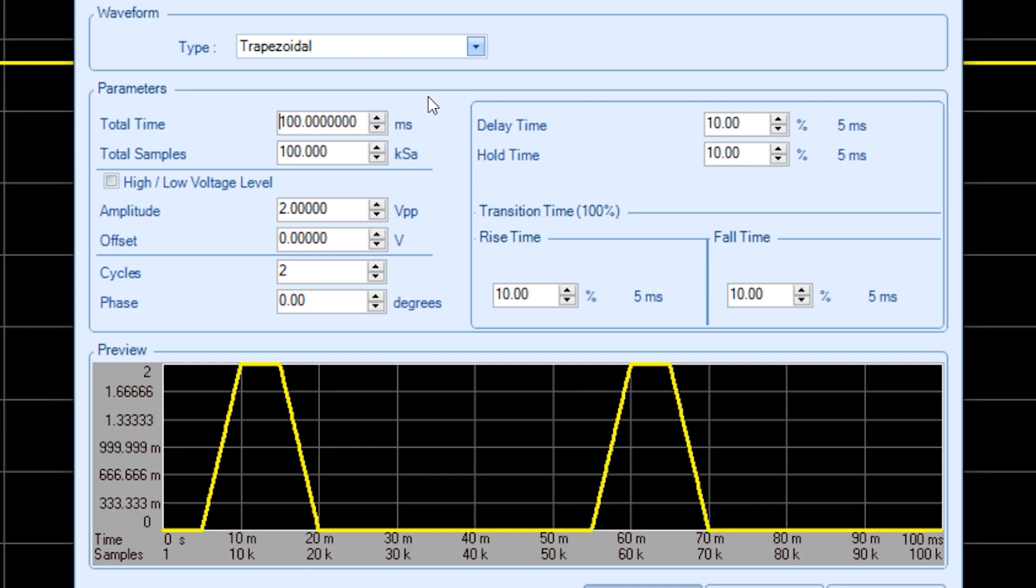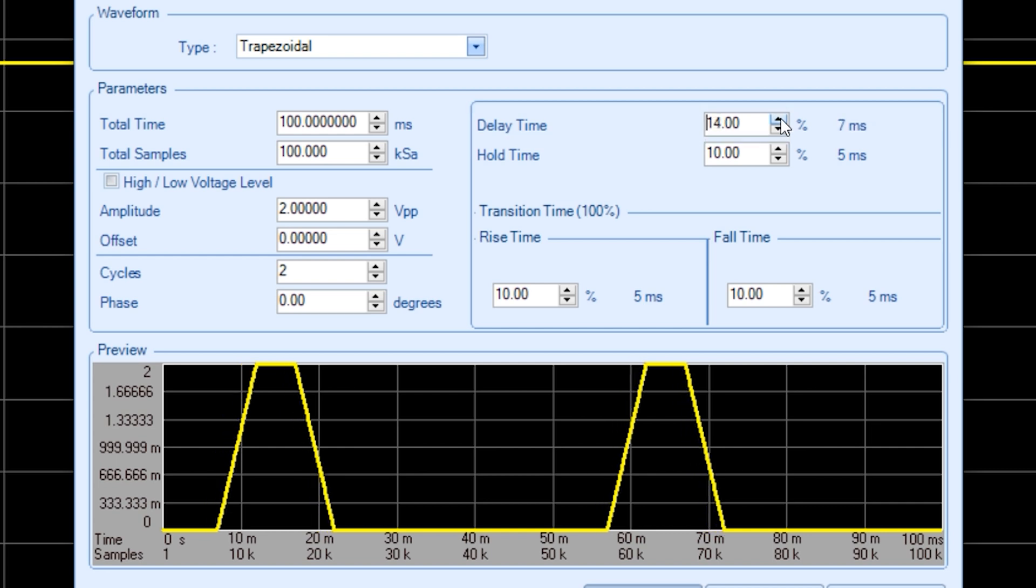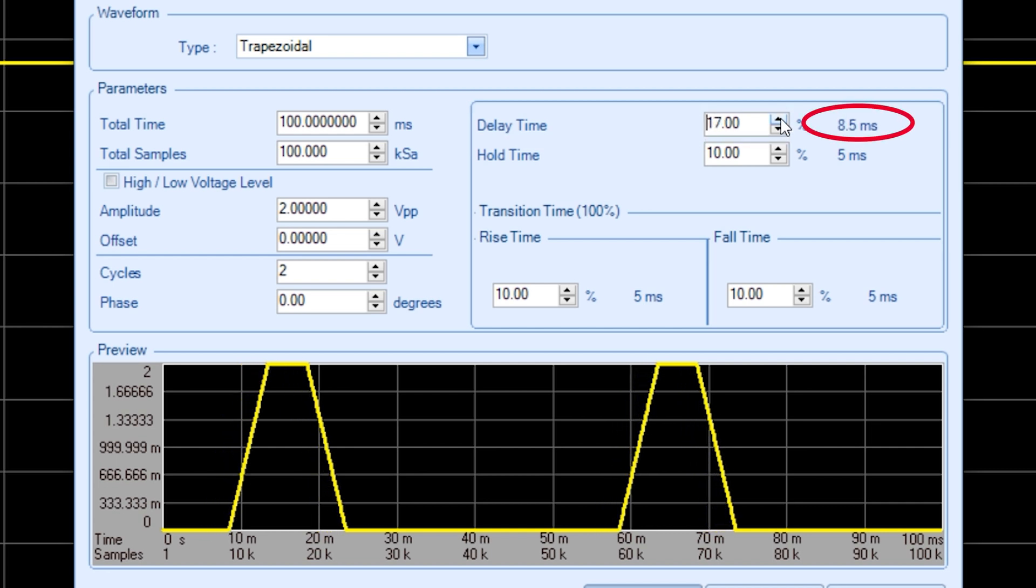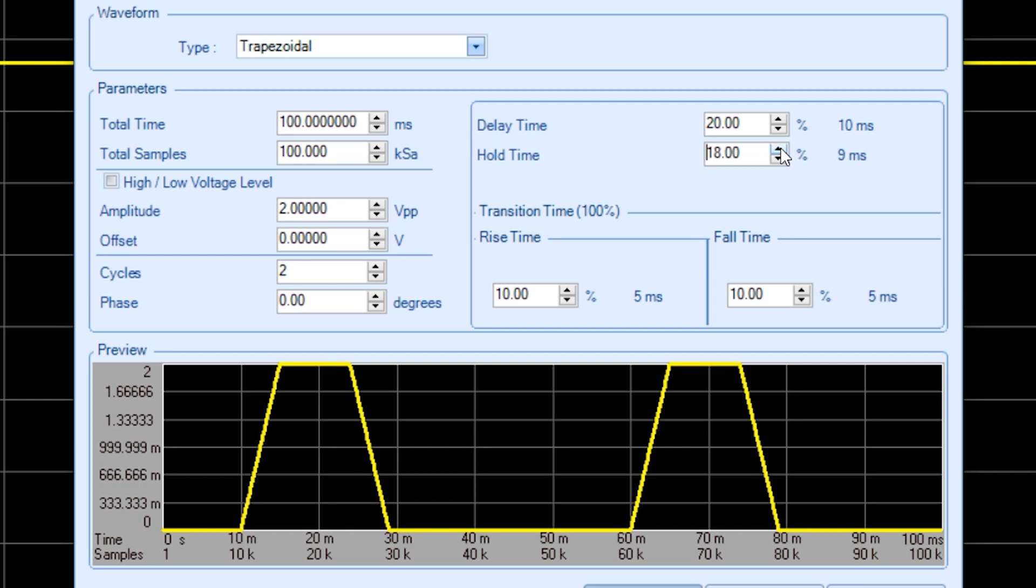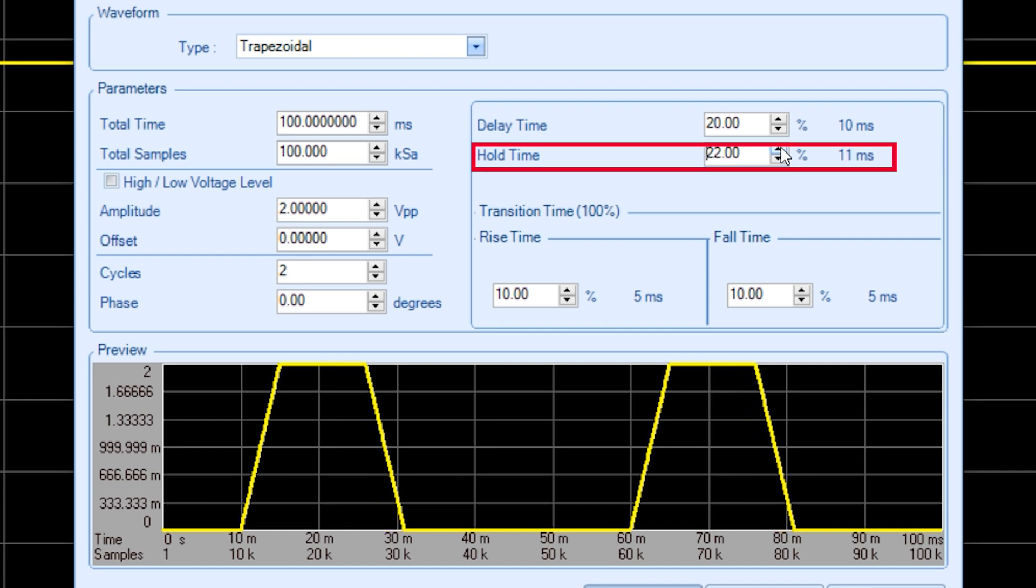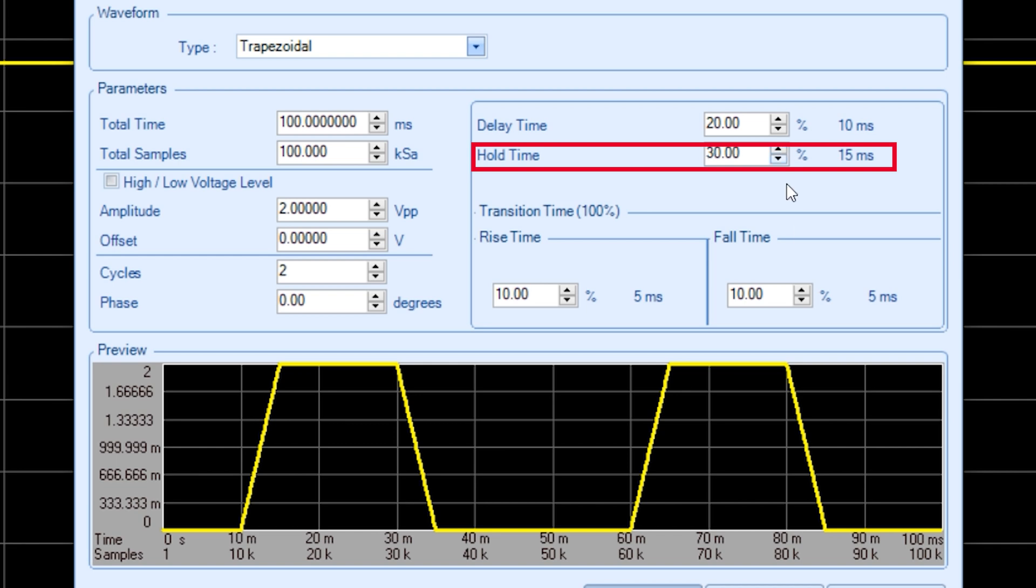I can set the delay time before I start to power up. Let's set it at 10 ms. I can change the hold time that we are at full power on the trapezoid. We will set that to 30% which is 15 ms.